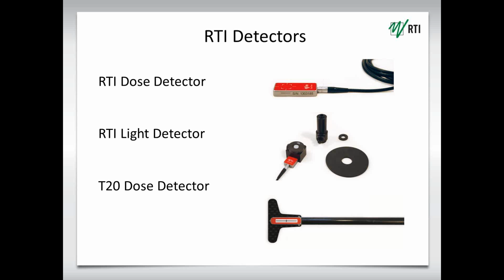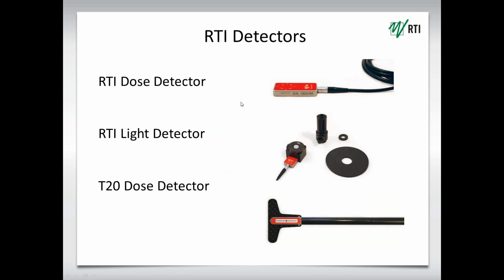If I go into the RTI detectors, we've got the RTI dose detector, which is a standard out there. It is better than ion chambers in the radiographic range for measuring anywhere from 1.5 millimeters of aluminum to 2 millimeters of copper. We have our RTI light detector, which measures luminance and illuminance, and it's been a standard for a long time. In addition, we brought in our T20 dose detector several years ago. You can use this in any fluoro beam. It doesn't affect the actual output of the fluoro. It doesn't affect the auto brightness mode. So you can go to a 6-inch mag or higher, and the kV and mA do not drive.